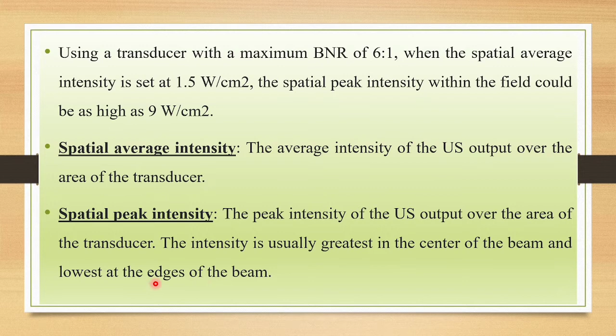So the intensity is usually greater at the center of the beam and lowest at the edges or periphery of the ultrasound beam. In this diagram, you can see this is the transducer and this is the effective radiating surface area. The spatial peak intensity will be more at the center of the ultrasound beam, and it will get less as it moves towards the periphery or edges of the ultrasound beam. So this is the beam non-uniformity ratio, the ratio of spatial peak intensity to the spatial average intensity.